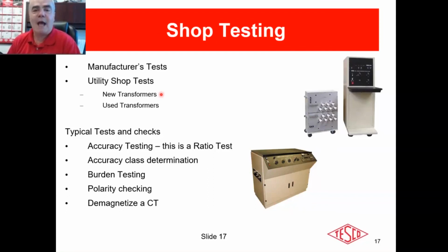How often does it need to happen to justify 100% testing? Well, if it happens one time on a $1 million a month customer, that may justify your testing for a whole lot of decades. All right. The manufacturers also do 100% testing, but again, a marking could be done incorrectly afterwards or before. Used transformers. Why would you want to test used transformers? The only reason you would want to test used transformers is if there is some sort of billing dispute, or if you're going to be returning a transformer to service.